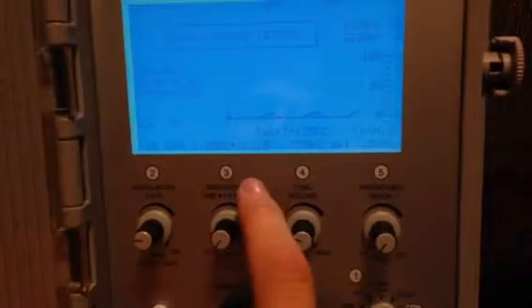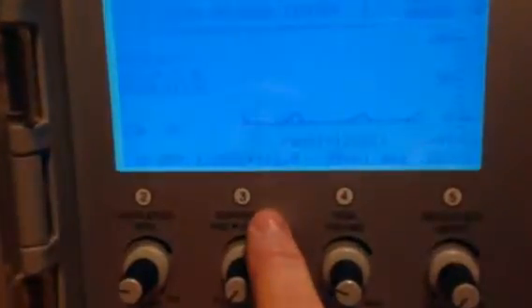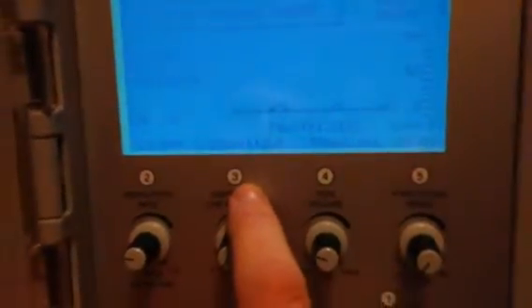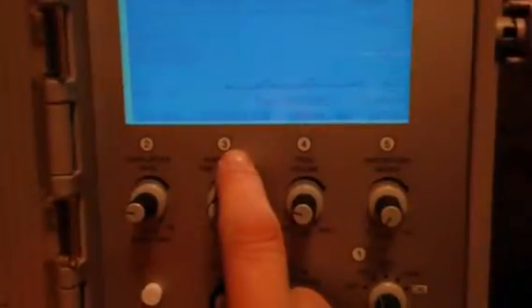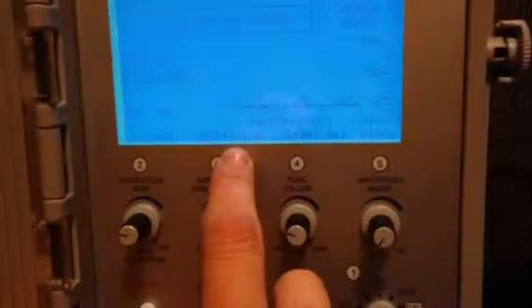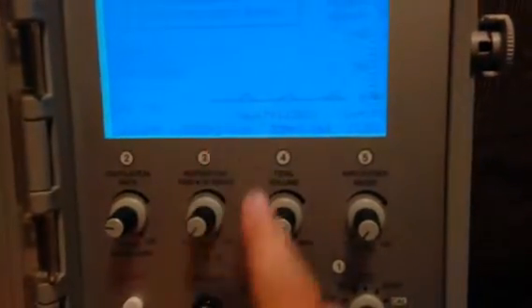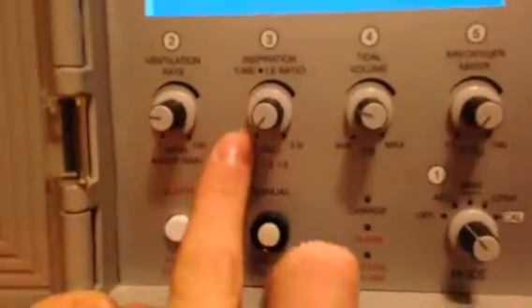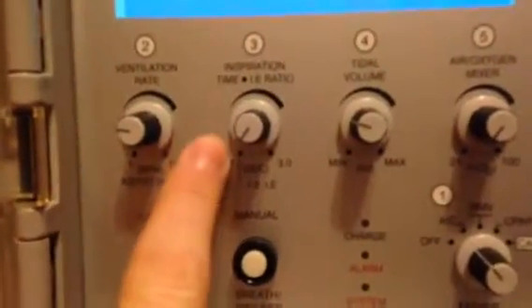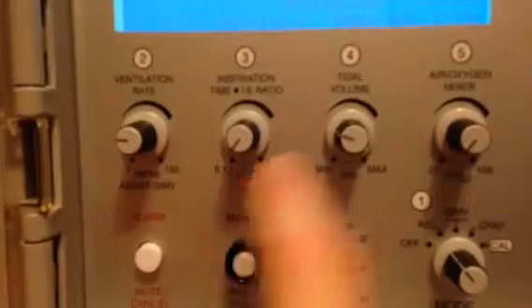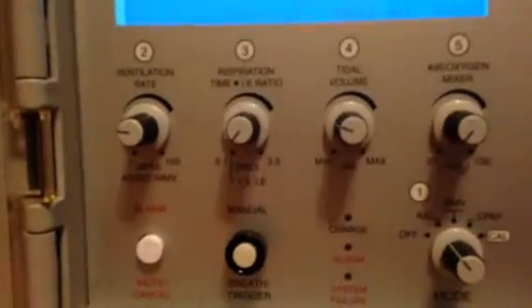Step 3, we're going to set the inspiratory-expiratory ratio. I'll go into a little bit about that later. But the I:E time, pretty much for all our transports, is always going to be 1 to 2. If you move the I:E knob all the way over into the far counterclockwise position, right there, it'll always come up in 1 to 2.